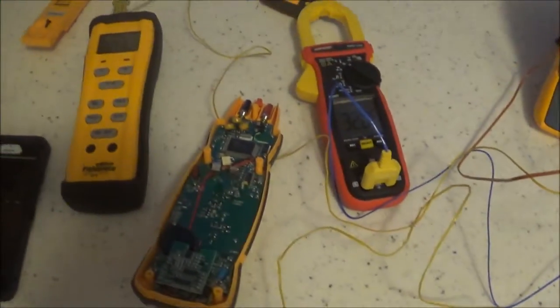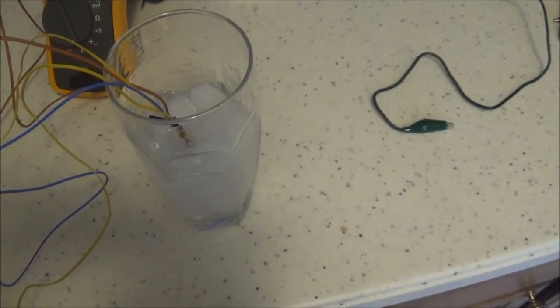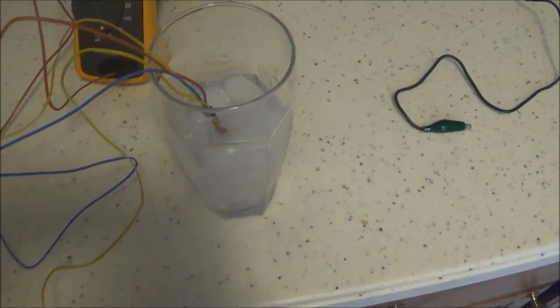I was calibrating all my meters on their temperature just to verify they were close to 32, so I've got all the leads tied together in crushed ice and water.